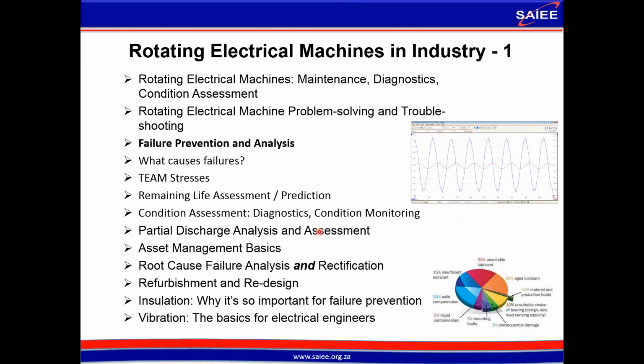So we'll look at maintenance, diagnostics, and condition assessment. In order to troubleshoot or prevent failure, we need to solve problems, and we need to know what causes these problems. So what causes the failures? We look at TEAM stresses. TEAM stands for thermal, electrical, ambient, and mechanical. We look at remaining life assessment or remaining life prediction, the difference between diagnostics and condition monitoring.